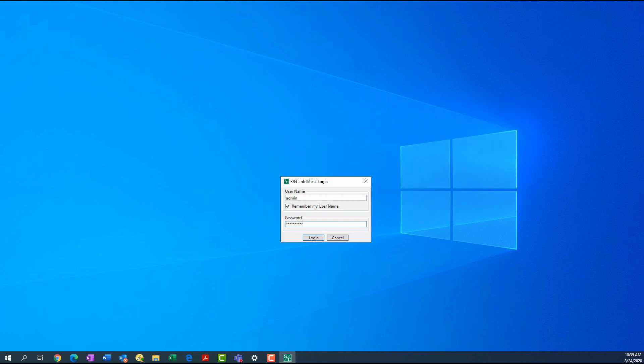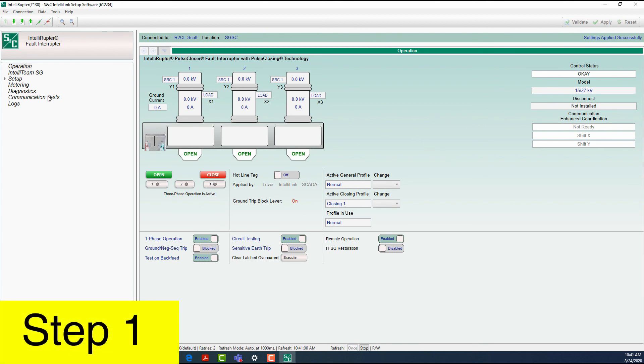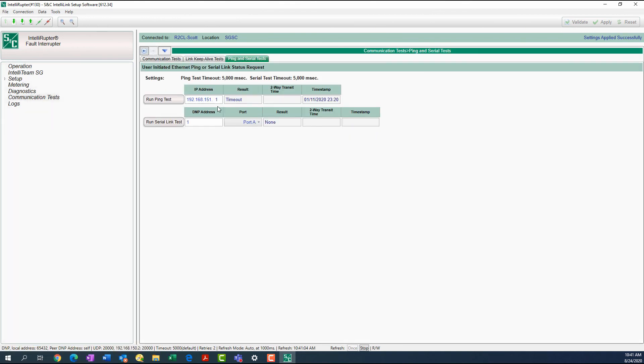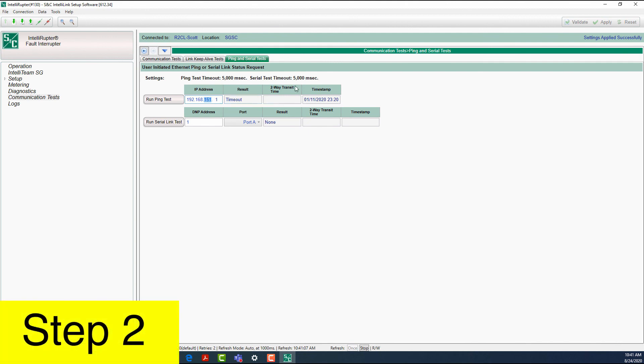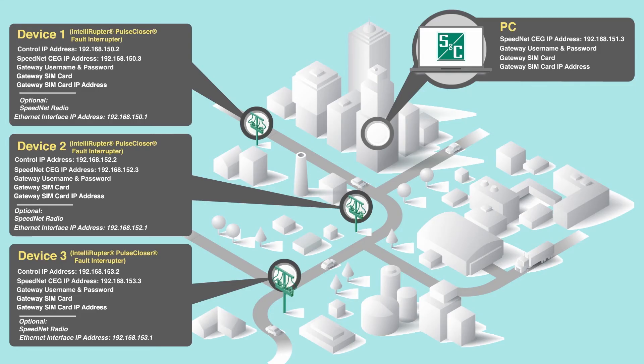When using the cellular network in conjunction with a Speednet radio network, carry out the following steps to confirm that the Intelliruptor fault interrupter is able to communicate with the other Intelliruptor fault interrupters connected to the Speednet radio network. Step 1: Use the Communication Tests tab to navigate to the Ping and Serial Tests sub-tab. Step 2: In the IP address box, enter the IP address of the Ethernet port of the radio on the route being tested. Step 3: Click on the Run Ping Test box to test the route. The results of the test will appear in the Results box. Step 4: Repeat the Ping test for all the Speednet radios on the private wireless network that are remote from the gateway.